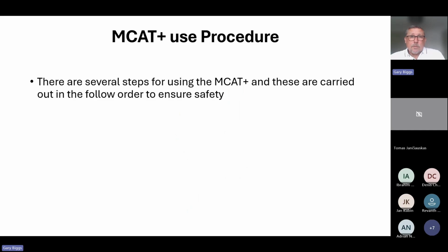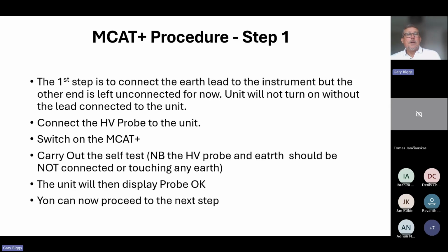So there are several steps for using the MCAT, and these have to be carried out in the following order for safety reasons. If they're not carried out in the correct order, then that could pose an issue for people working upon the systems. And the MCAT itself has been designed to lead you through the order that you need to do things. So the first step you need to do is connect the earth lead to the instrument.